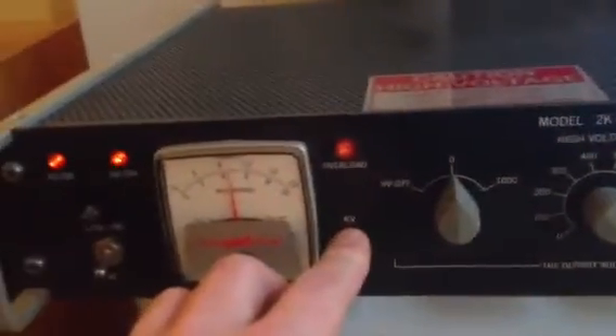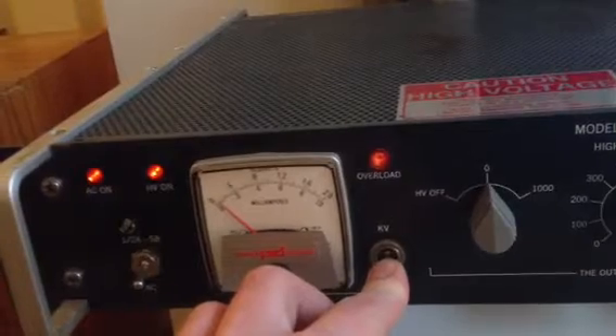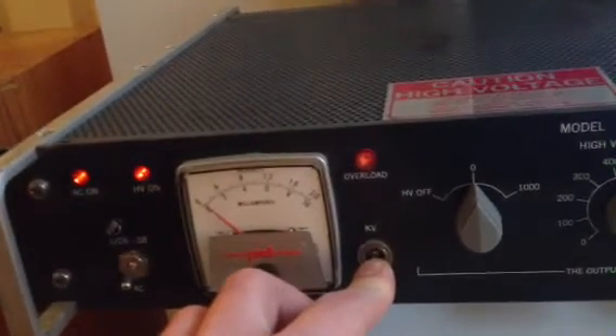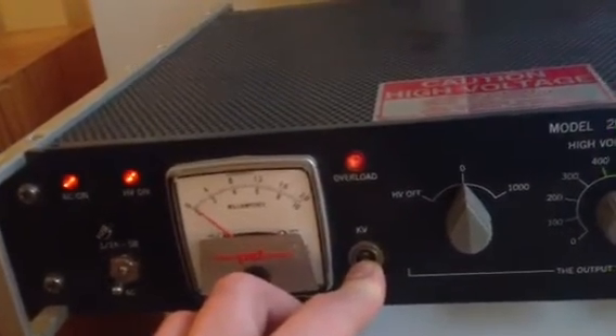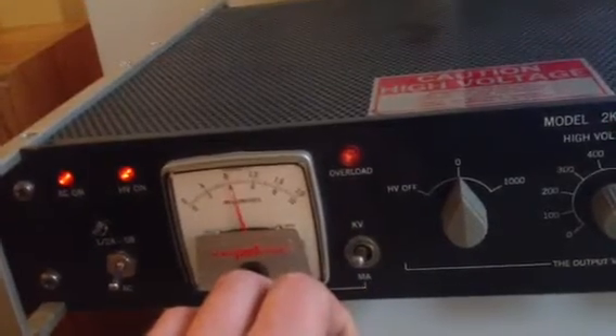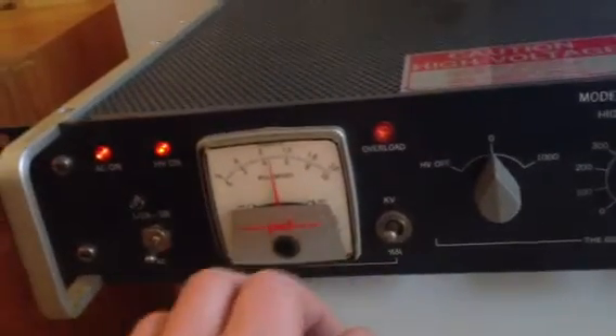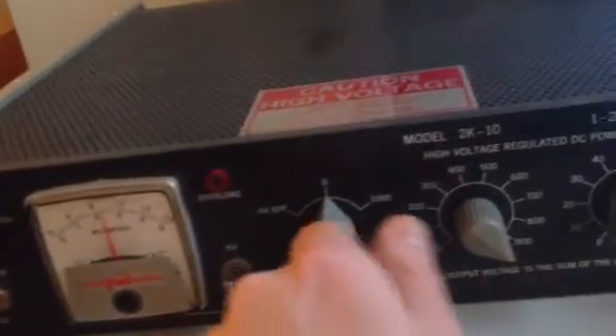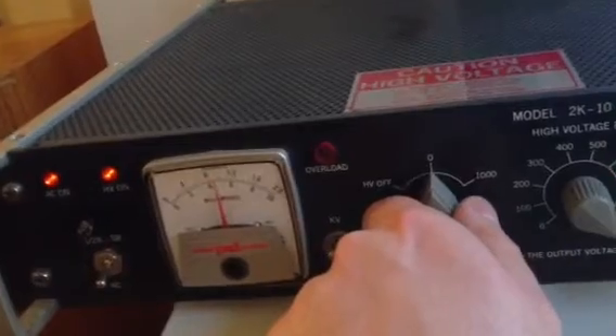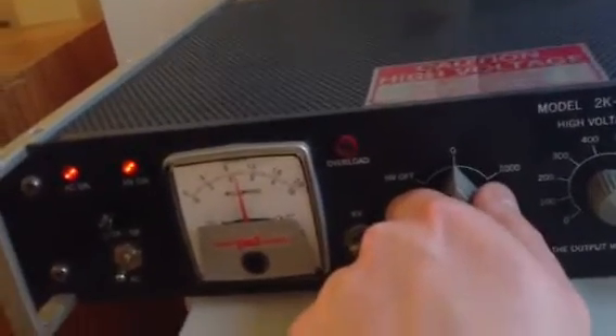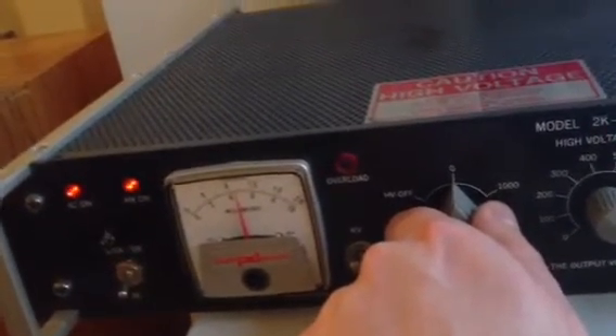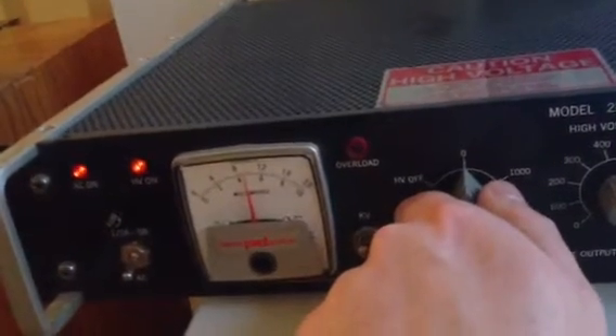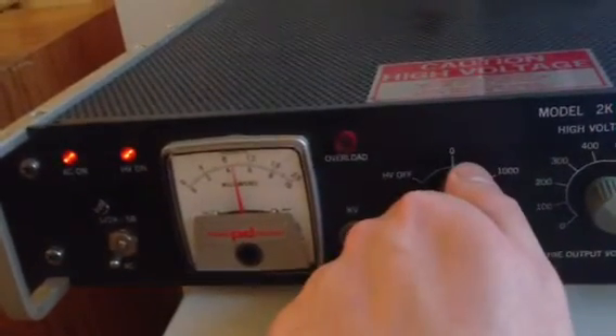Just to prove that I'm not faking, let's just try measuring the current output. Even with the PMT connected, the current is negligible. I believe this one has a fairly high resistance in its dynode chain. So let's just try. Now the overload neon is off, so that's probably just due to charging up the main capacitor. It probably comes on at the start while there's still charge going into the tank.